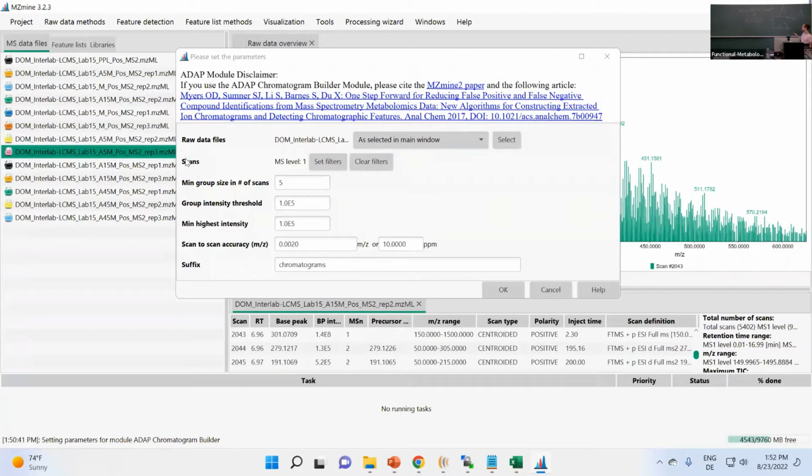What can happen in some cases is, for example, that due to some filtering or some deviation in the mass detection, the shape can look like this. And here we wouldn't have 5 consecutive points above a certain threshold, and then this trace will be discarded. So this can already influence your results later on. So it's good to check how stable my instrument is along the whole acquisition.